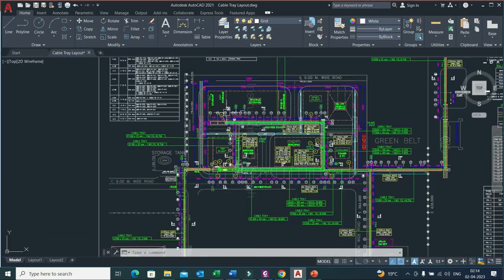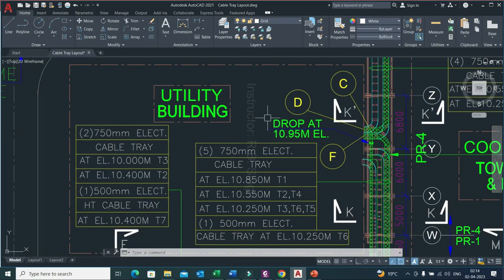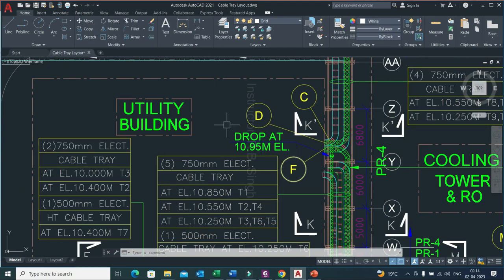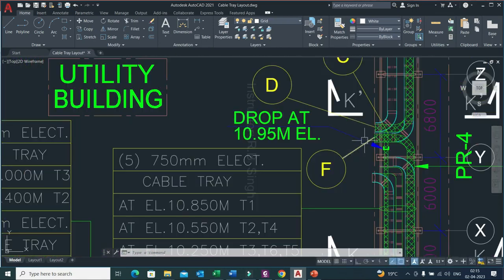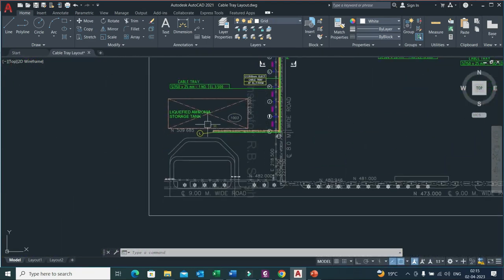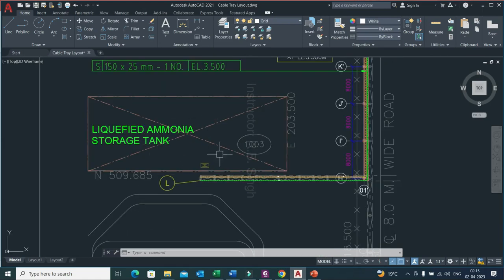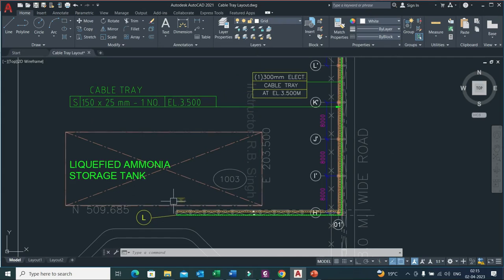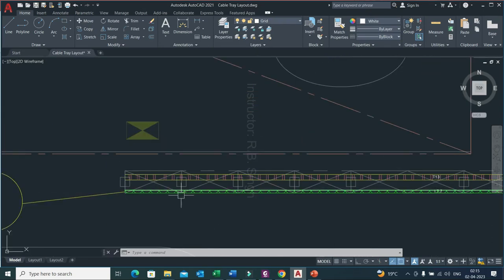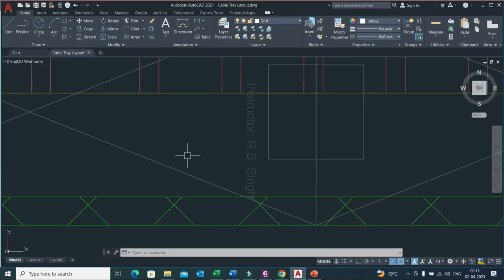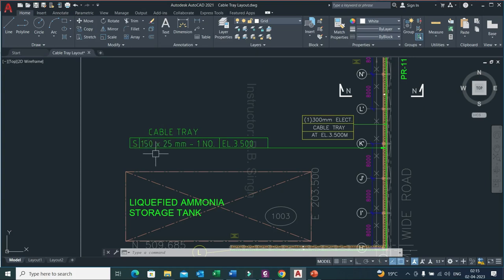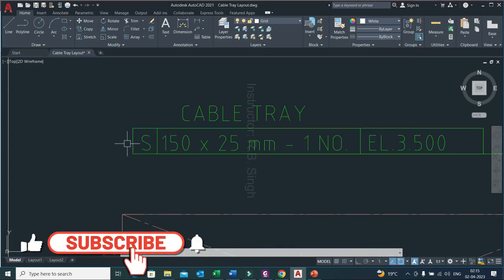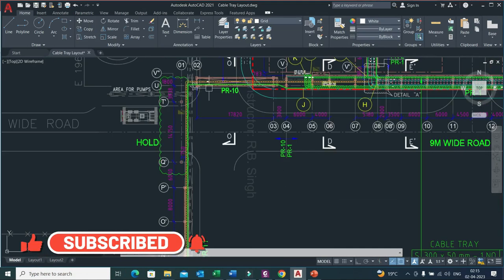Let's look at this layout in detail in the AutoCAD file. You can see the utility building where the control room is — all the cables are coming toward this area, with all end portions of the cable trays at this location. From every area, like the liquefied ammonia storage tank area, junction boxes send multi-pair cables toward the control room. The electrical cables maintain minimum spacing. The cable tray going toward the control room here is 150 mm width, 25 mm height, at 3.5 meter elevation, used for signal purpose.